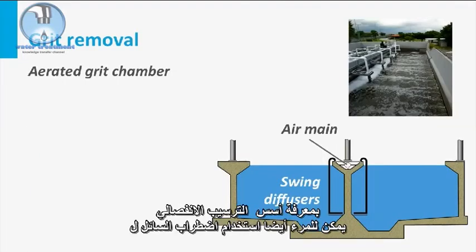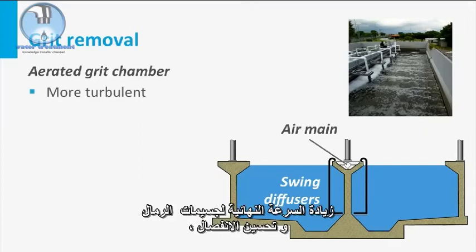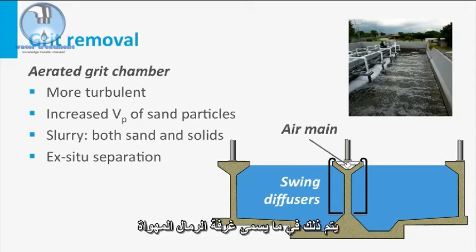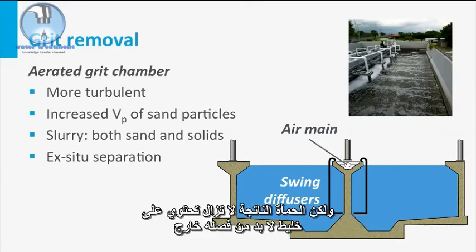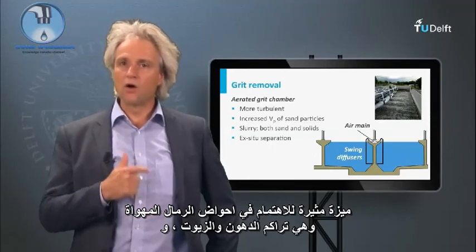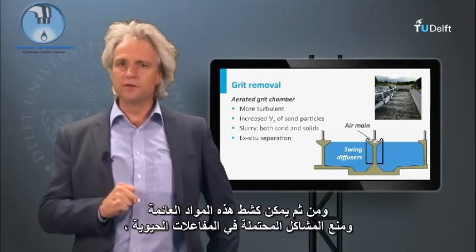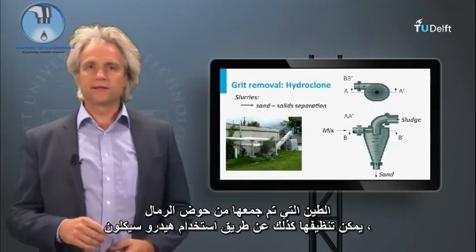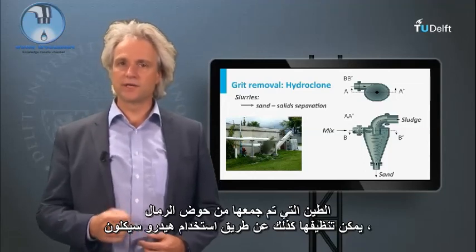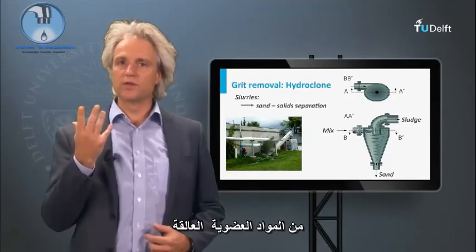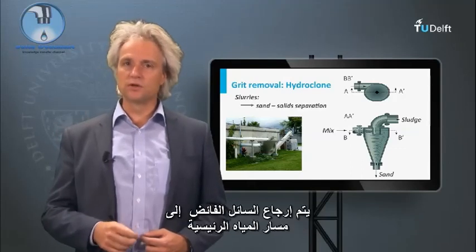Knowing the fundamentals of discrete settling, one can also use liquid turbulence to increase the terminal velocity of the sand particles, enhancing separation. This is done in a so-called aerated grit chamber. Most organics will be separated from the sand particles, but the produced slurry still contains a mixture that needs to be separated outside the tank. An interesting advantage of an aerated grit chamber is the accumulation of fat, oil and grease at the top of the chamber, which can be skimmed off, preventing possible problems in the bioreactors. The collected slurry can be further cleaned by applying a hydrocyclone, which creates a concentrated downward stream with sand for discharge and a lighter upward stream with organic suspended solids. The liquid overflow is returned to the main water stream.